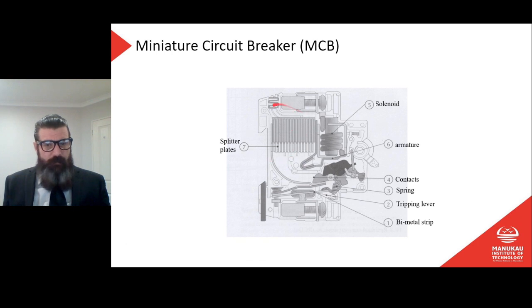And lastly, number 7, we have the splitter plate. So our arc is going to be directed through here. In order for an arc to be created or maintained, it has to jump across each one of those individual plates there. It obviously becomes increasingly difficult, and therefore it's going to assist the extinguishing of the arc, which is what we're trying to do, right? Because there's no point in opening the contacts and then letting that arc continue uncontrolled.